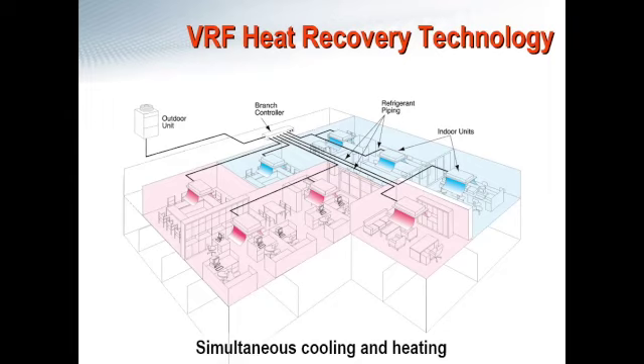We like to look at vertical applications for heat pump, whereas with heat recovery, as you're going to see in this slide, we like a horizontal application. So you might be servicing the eastern and the western facades of a building, really maximizing your load diversity in that space and allowing as much heat recovery as possible to occur to really save your compressor from doing any extra work, anything that it doesn't need to do.